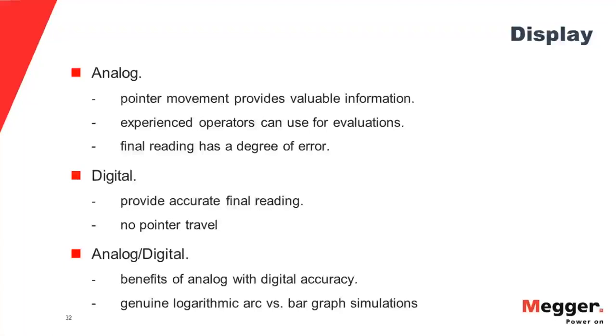If the pointer is stuttering, falling back, something like that, there's a problem with the insulation, something's going on, it might be arcing, for instance.